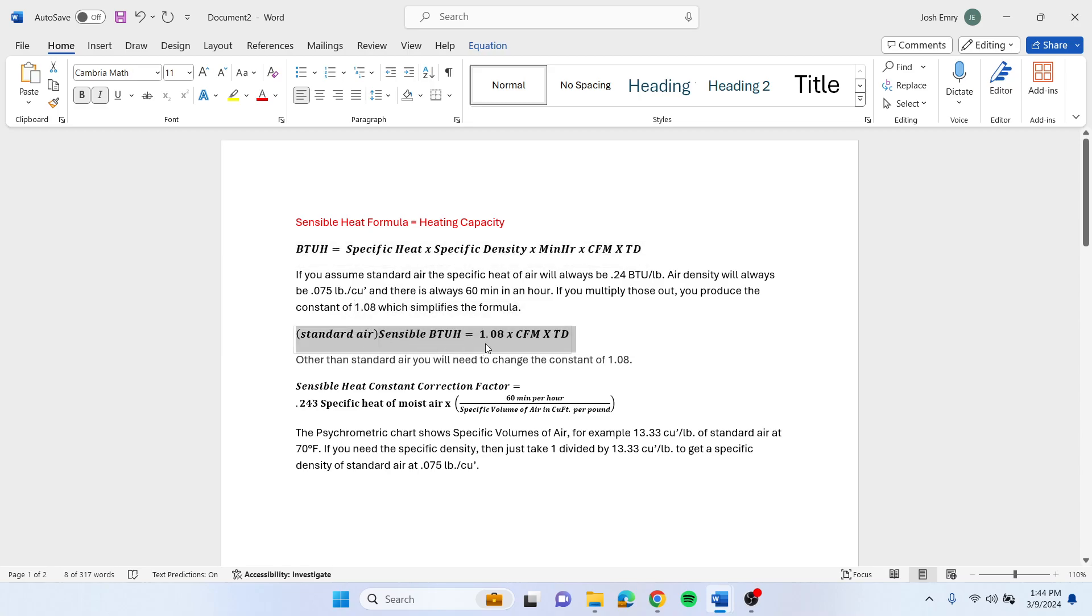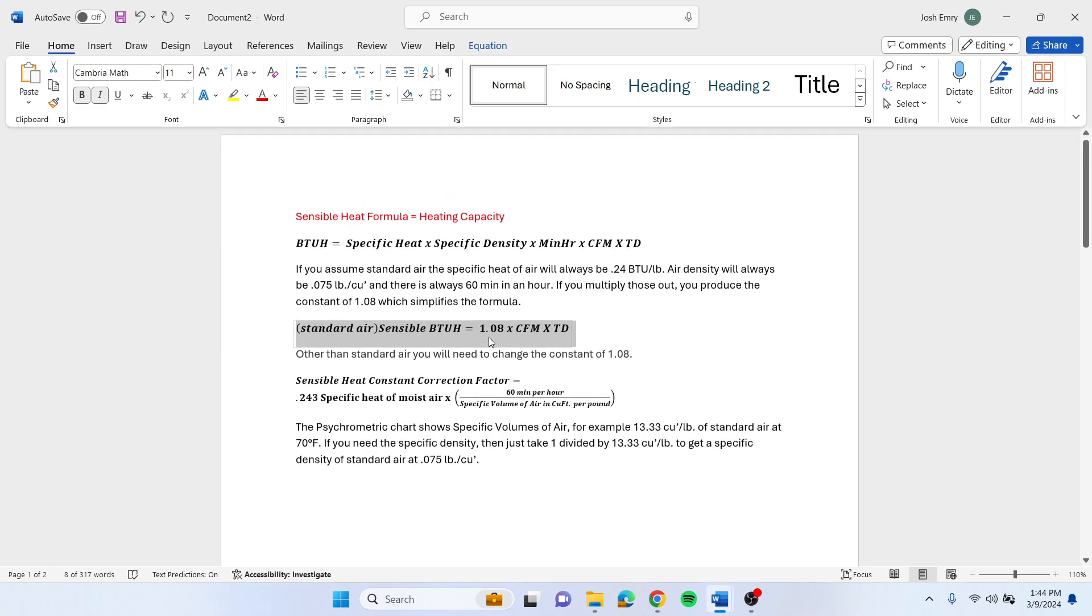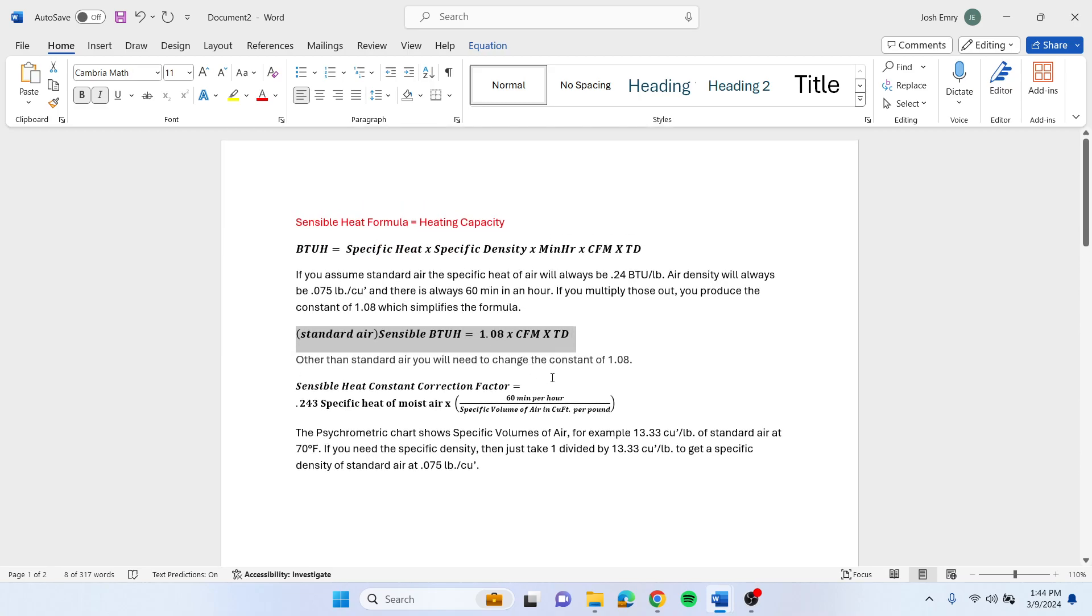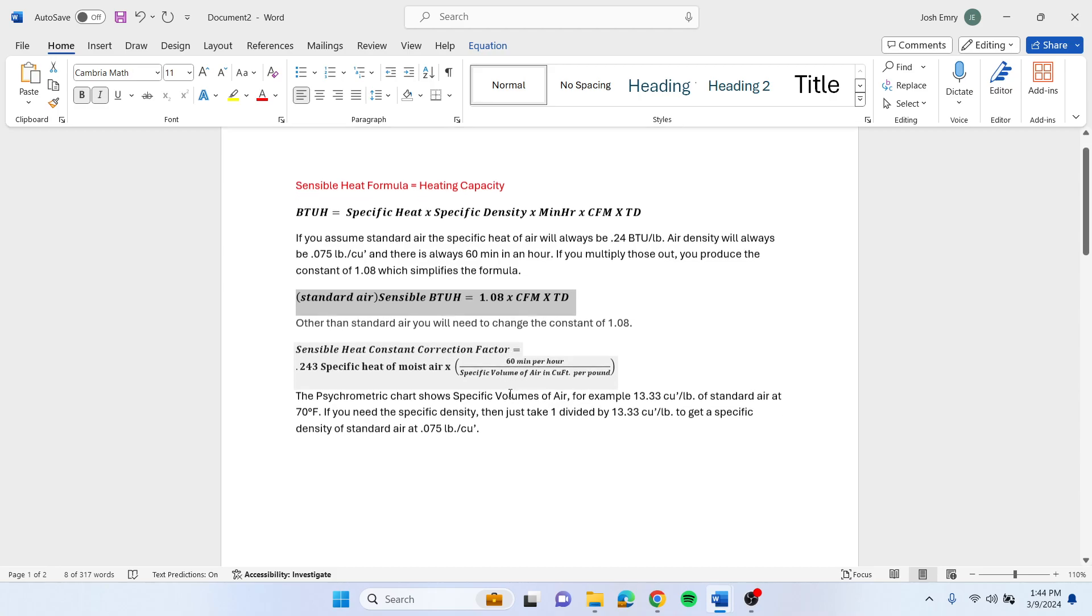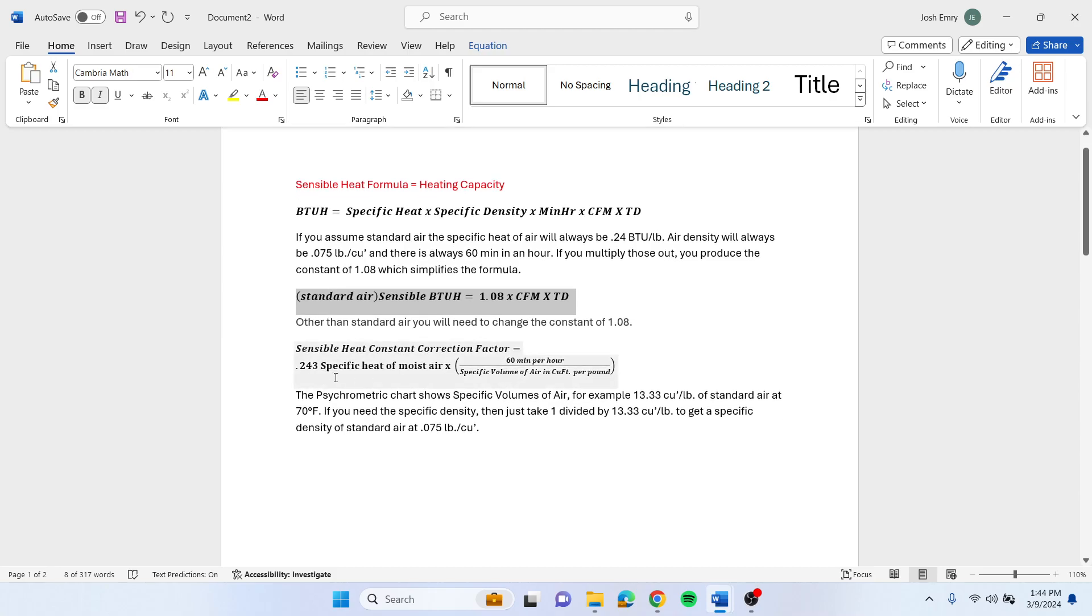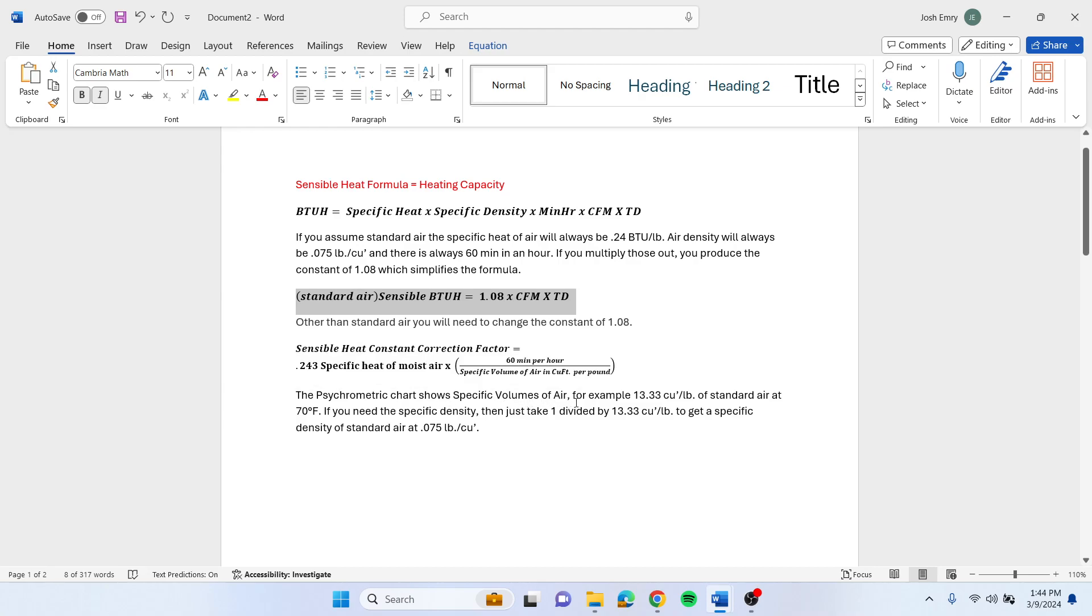Other than standard air, you have to change the constant of 1.08. The sensible heat correction constant correction factor equals 0.243, the specific heat of moist air, which is your 0.24 BTUs per pound, times your 60 minutes per hour, divided by the specific volume of air in cubic feet per pound at that temperature.